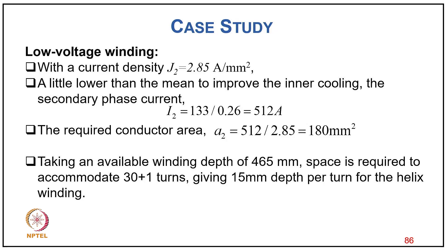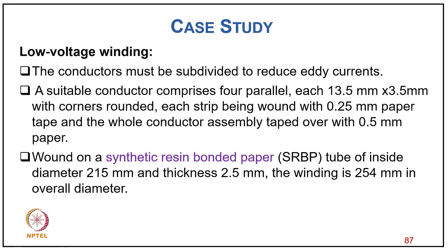For low voltage winding design with 465 mm winding depth and 30+1 turns, giving 15 mm depth per turn in the main helix winding: the conductor must be subdivided to reduce eddy currents. A suitable conductor comprises 4 parallel strips of 13.5×3.5 mm with rounded corners, each wound with 0.25 mm paper tape and the whole assembly tapped with 0.5 mm paper, wound on an SRBP tube of 215 mm inner diameter and 2.5 mm thickness. Overall LV winding diameter is 254 mm.